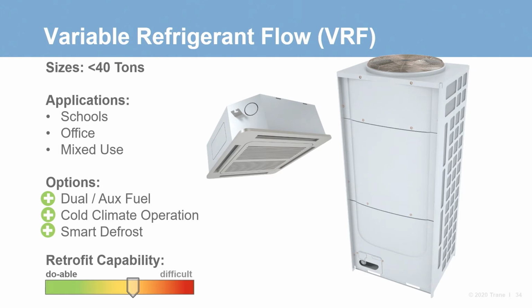If the building has no air conditioning and you're comparing various systems on ease of retrofit, VRF might rise to the top. Being able to run small refrigerant lines through the building is typically easier than running ductwork through the building. On the other hand, if you're replacing an existing cooling system, say a PTAC, RTU, or any hydronic system, it's likely easier to use a heat pump of the same style instead of retrofitting to VRF.